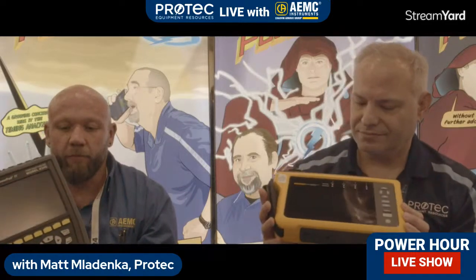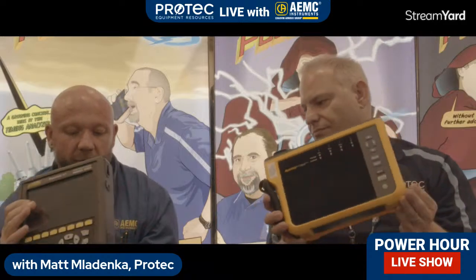For you NETA guys, let's talk differences. Class A is kind of misunderstood in the U.S., it's not an easy thing. But one thing you can guarantee, if an instrument says Class A, and we've synchronized the clocks, all our measurements out of this and this are identical because they have to be. That's one of the biggest parts of Class A, it standardizes measurement methods and mathematical formulas used for calculations. Sample rates are all similar or exact, and the math to derive our different measurements is exactly the same across all our Class A instruments. So that's something to compare right off the bat when looking at price, there's a bigger difference there.